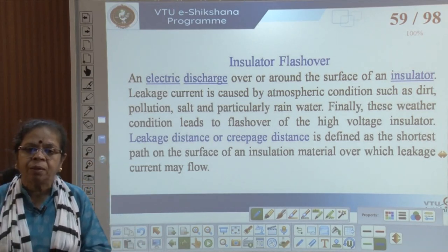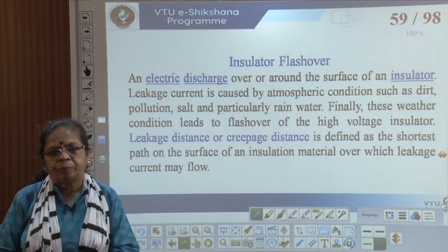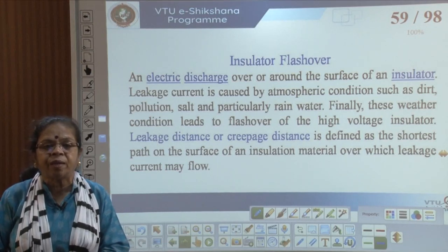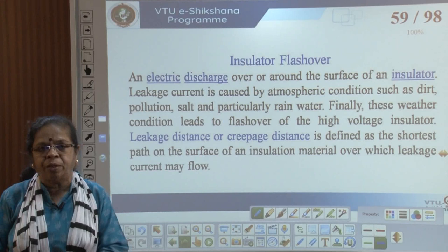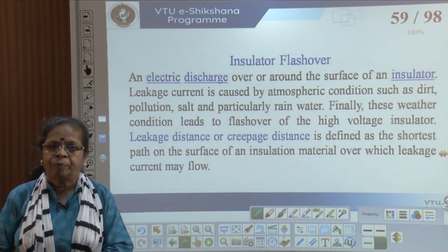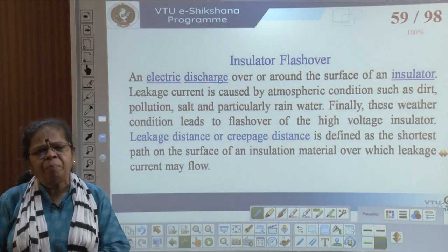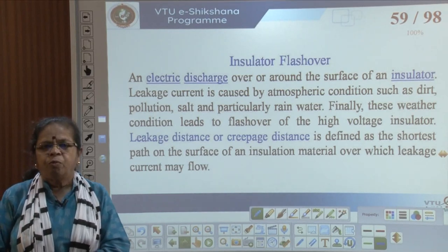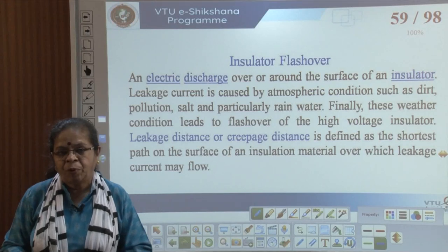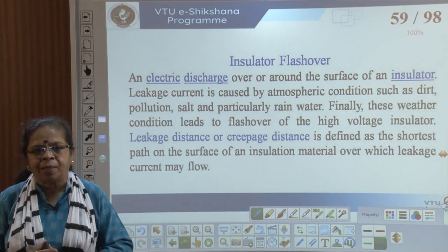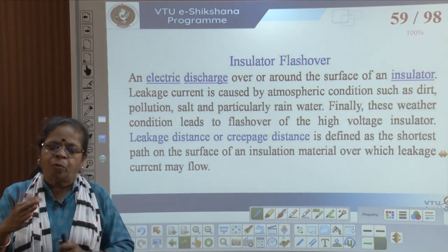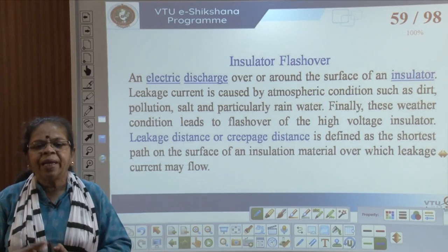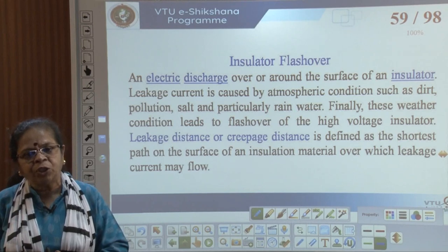With insulators, we have an interesting phenomenon called insulator flashover. An electric discharge over or around the surface of an insulator is called insulator flashover. The leakage current is caused mainly by atmospheric conditions — dirt, pollution, salt, and moisture — which make the surface of the insulator conducting. Rain, hail, and similar weather conditions lead to flashover of the high-voltage insulator.